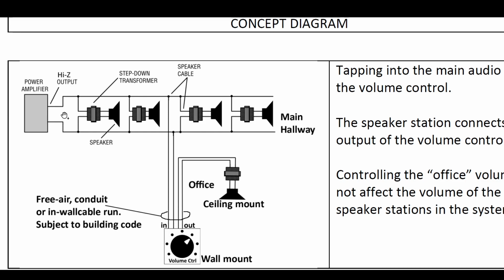Here is the location of the main feed, which would be maybe on one end of the hallway. Then you're going to run it from a box. The wire continuously pulls out as you pull on it, and you keep pulling and run it right in the ceiling space, right to the end of the hallway, and tie it somewhere, then start pulling the service loops.